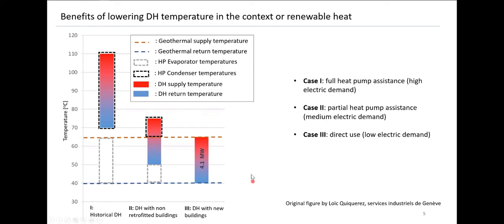The last case, which is the most favorable, is if we have a district heating network that can operate at the level of the geothermal resource. We can make direct use of it. If the return temperature of the district heating network is 40 degrees, we can use directly this 4.1 megawatt without any heat pump assistance — just pumping energy — resulting in much lower electricity consumption. This gives you one idea of the benefits in the context of renewable heat.